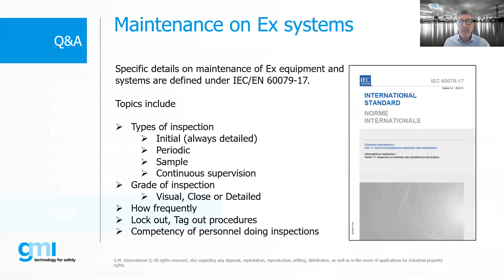17 standard. Yep. How about using a removable gland plate in an EXD enclosure? Yeah, EXD enclosures typically don't have removable gland plates because EXD boxes are cast enclosures, right? Typically sand cast, pressure cast. However, EXE enclosures do have gland plates, so certainly that is an option. The reason for gland plates primarily is to make it easier to install cable glands or to punch the holes in the field to install cable glands. And if you make a mistake with a gland plate in punching a hole that's either too big, too small, or not right, you can always replace the gland plate as opposed to having to replace the entire enclosure. So certainly gland plates are common, but not for EXD.